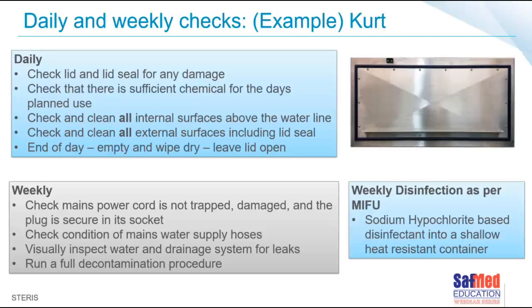And we will always make sure that the chemical levels, or your enzymatic detergent levels, are correct and it's enough for the use for that day. Most times we'll find that there's no detergent in the can, and everybody has continued using it. They find out that the instruments are not coming out clean. The first check is to always check the detergent levels. A lot of the ultrasonic cleaners do not have a sensor that picks up the level of detergent because there's only a pipe running in there and a pump pumping it out. So always check that. Then throughout the day, please wipe and clean all internal surfaces above the waterline to prevent any residue or buildup of the endotoxins and other buildups.